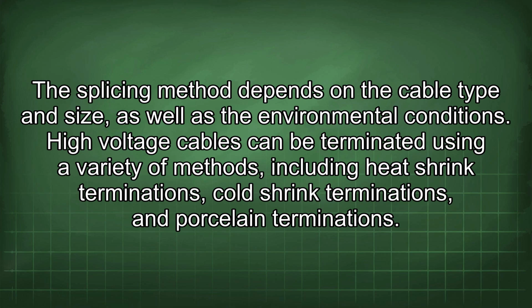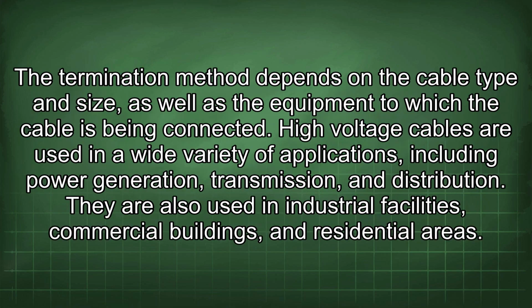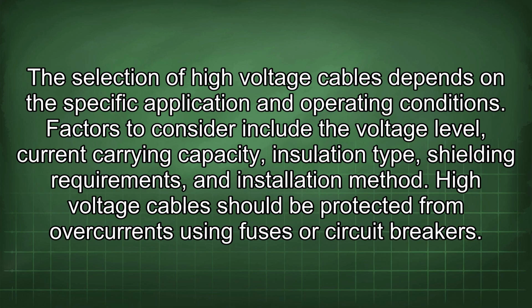High voltage cables can be terminated using a variety of methods, including heat shrink terminations, cold shrink terminations, and porcelain terminations. The termination method depends on the cable type and size, as well as the equipment to which the cable is being connected. High voltage cables are used in a wide variety of applications, including power generation, transmission, and distribution. They are also used in industrial facilities, commercial buildings, and residential areas. The selection of high voltage cables depends on the specific application and operating conditions. Factors to consider include the voltage level, current carrying capacity, insulation type, shielding requirements, and installation method.